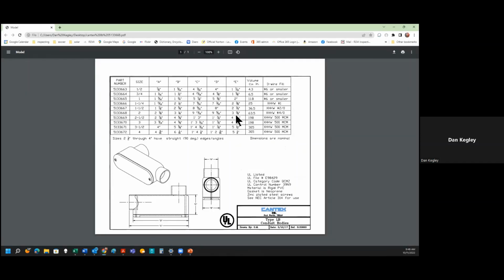So when we go to the manufacturer of that box, whether it's a PVC box or an LB conduit, you'll end up with something like this, and it's got this big UL stamp listed on here that is UL listed. But you have to read the fine print as far as what it's listed for. In this case, it says UL listed, the UL file number, category number, control number. And so in order to figure out what this thing's actually been tested for, because that's what UL is all about, is testing it for different uses. And this has not been tested to be used as a junction box with receptacle connectors, those kinds of things. That's not its design.